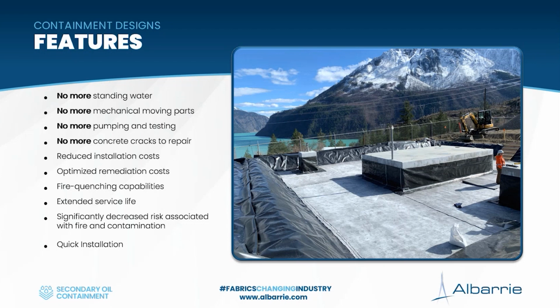The other thing that's very favorable about this system, especially when retrofitting existing substations where there might be things buried that you didn't know were there or that aren't on any drawing, is that you can make changes on the fly as it's being constructed. If a new foundation is discovered or needs to be added, you can basically use a box cutter to make changes. We can flexibly adjust the containment so the project keeps moving and doesn't get delayed.